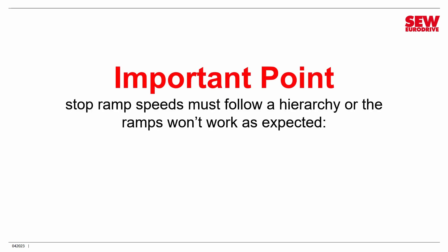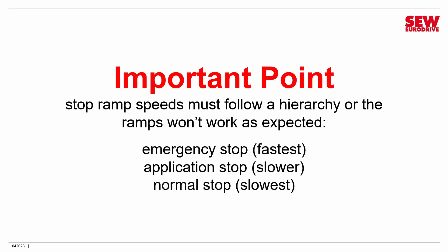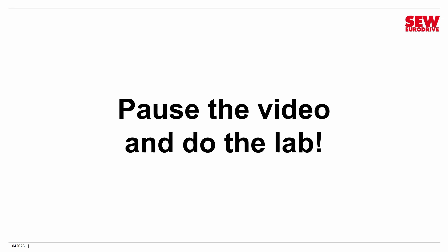An important point: stop ramp speeds must follow a hierarchy or they won't work as expected. The most emergency stops need to be the fastest. Emergency stop should be the fastest, application stop a little slower, and normal stop the slowest. If you don't follow this hierarchy, the system does odd things. If you see odd stop behavior, check your different ramps — you may have violated the hierarchy. Now pause the video, do the lab, and come back for the walkthrough.